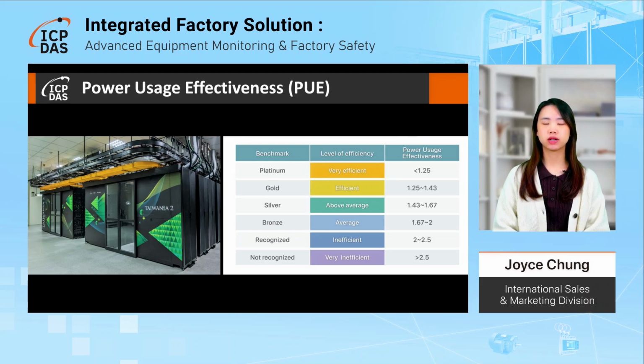You may wonder what is PUE. PUE is a crucial metric to measure energy efficiency in data centers. It compares the total facility energy consumption to the energy used by IT equipment. As we can see in the table, the lower the PUE value is, the better the efficiency is.